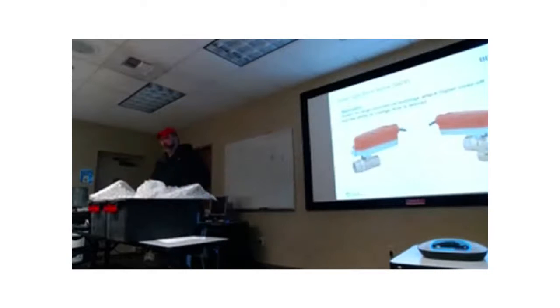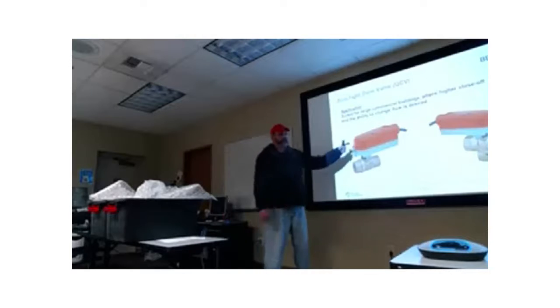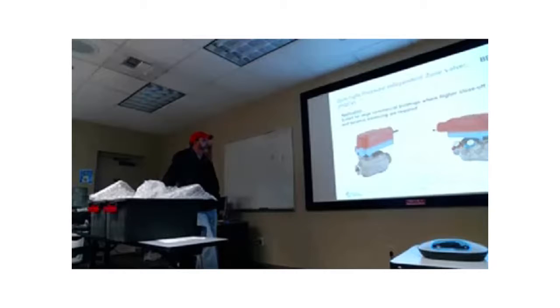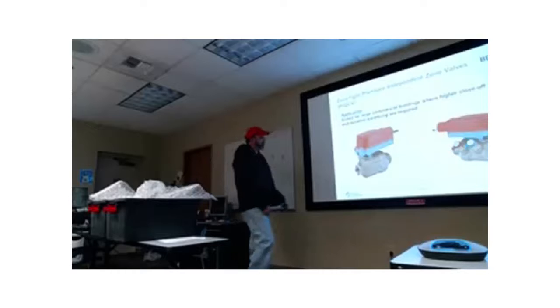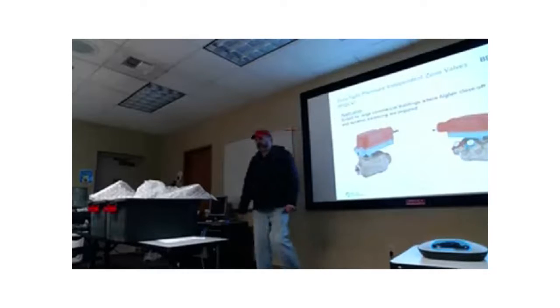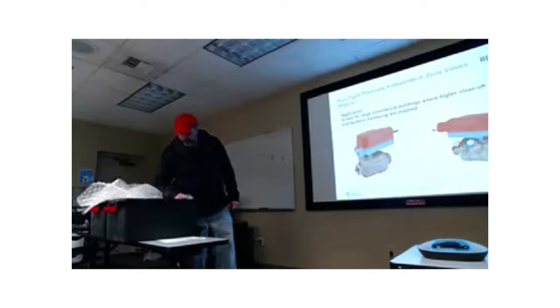We said it's a relatively energy saving device. I don't know if you guys have ever seen our old zone valve, our little pop tops. We designed this actually to get rid of those. So this is actually our valve, and we're going to be putting these in there. Just going on, we make a pressure independent version of that zone type, and it looks like this. I won't pass it around, but it basically works the same way as the PICCV that I just showed you.